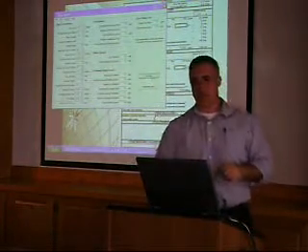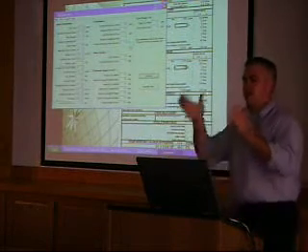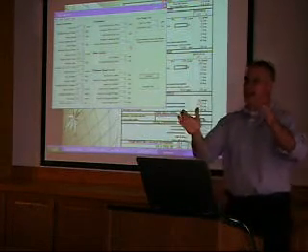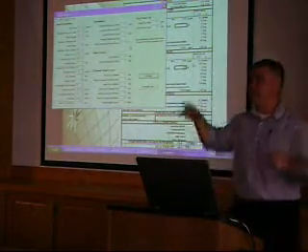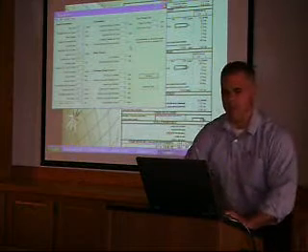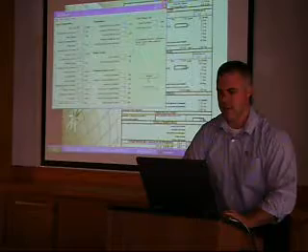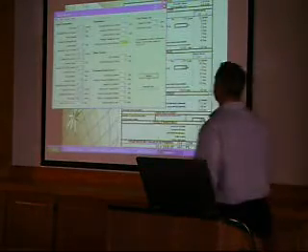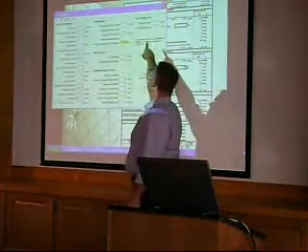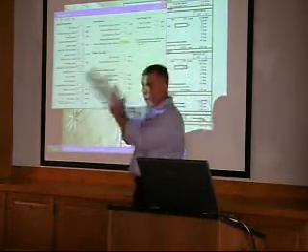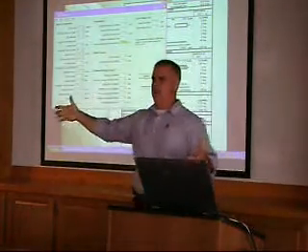Okay? And I want you to take note of this here too. The difference on the 50-foot lateral from the beginning to the end, you want no more than 10%, it's 1%. Let's see what happens when I bump it up to quarter inch. Let's go to the other extreme with sizes. Okay. 1.73 gallons per minute per orifice. Total system flow rate on one lateral is 37. Let's call it 40. That's 80 gallons a minute.